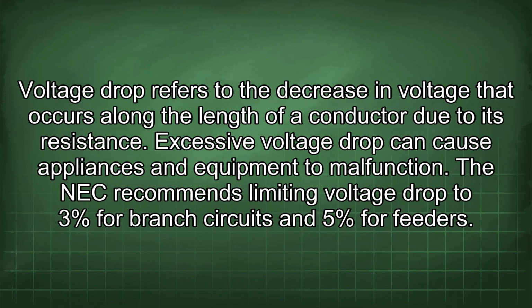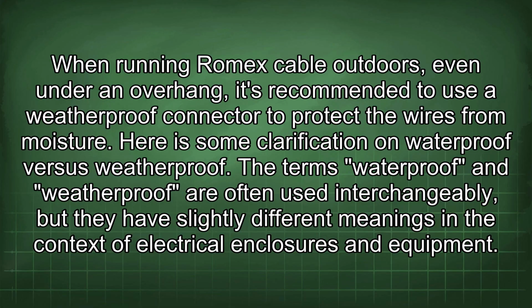Voltage drop refers to the decrease in voltage that occurs along the length of a conductor due to its resistance. Excessive voltage drop can cause appliances and equipment to malfunction. The NEC recommends limiting voltage drop to 3% for branch circuits and 5% for feeders. When running Romex cable outdoors, even under an overhang, it's recommended to use a weatherproof connector to protect the wires from moisture.